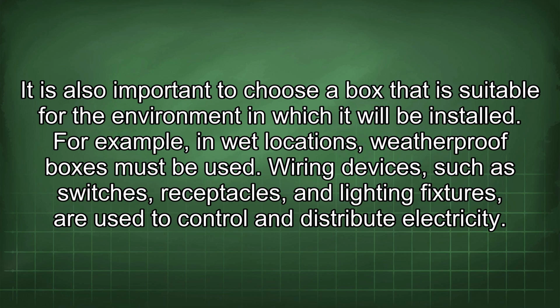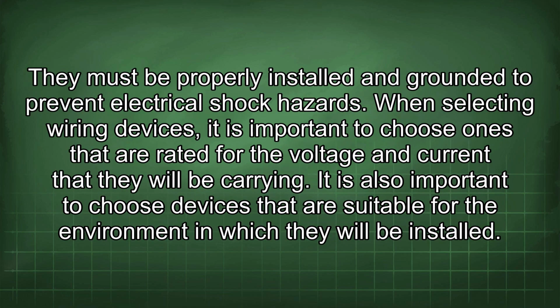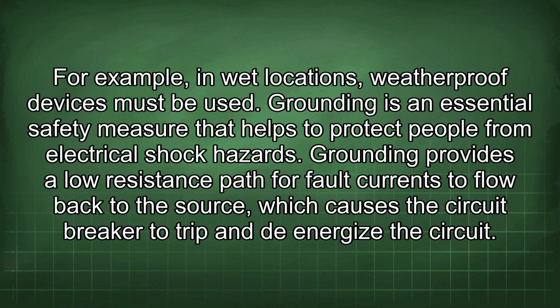Wiring devices, such as switches, receptacles, and lighting fixtures, are used to control and distribute electricity. They must be properly installed and grounded to prevent electrical shock hazards. When selecting wiring devices, it is important to choose ones that are rated for the voltage and current that they will be carrying. It is also important to choose devices that are suitable for the environment in which they will be installed. For example, in wet locations, weatherproof devices must be used.